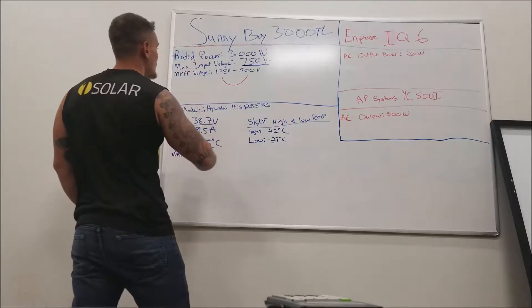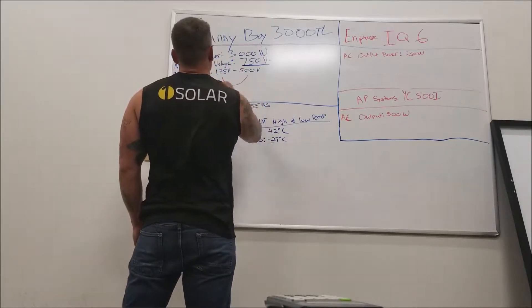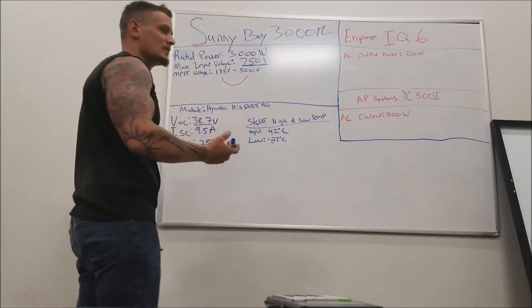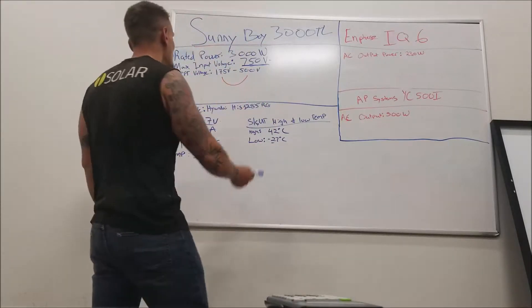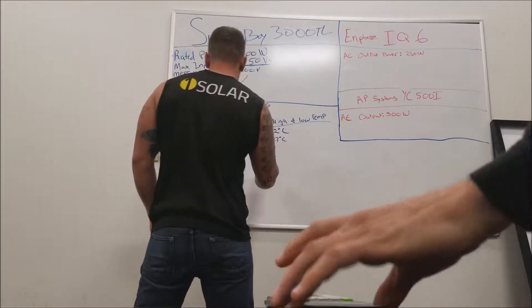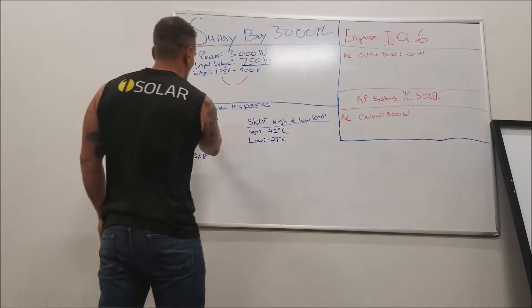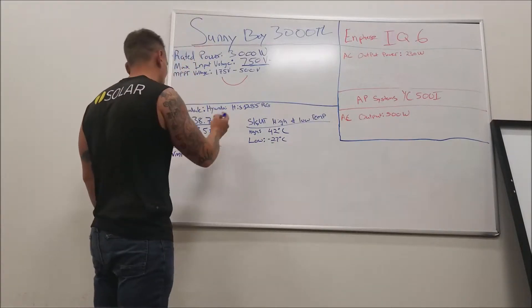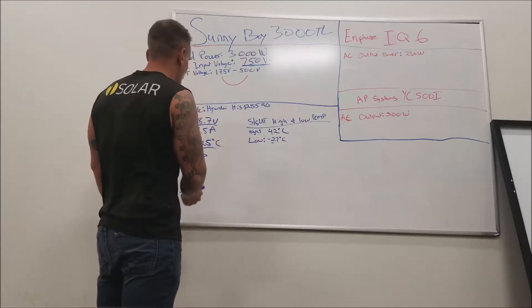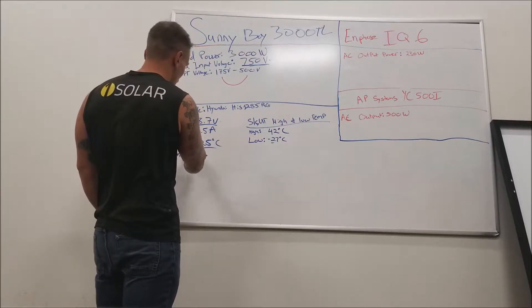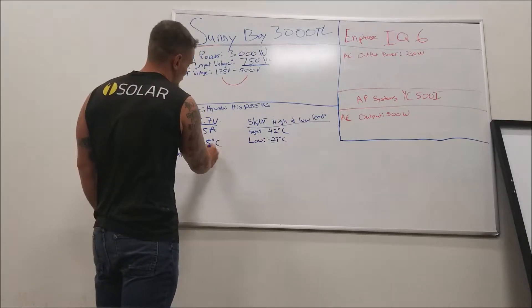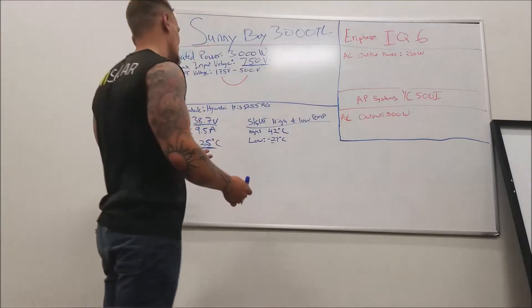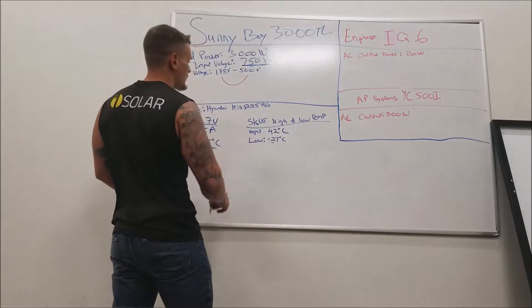What we're worried about with our string sizing is our maximum voltage. If we go over that, the inverter is going to explode. So we're going to look at our module's VOC — the voltage at open circuit — which is 38.7 volts. That's assuming we're at 25 degrees Celsius, which in reality we're not — that's standard testing conditions. So we need to correct that.